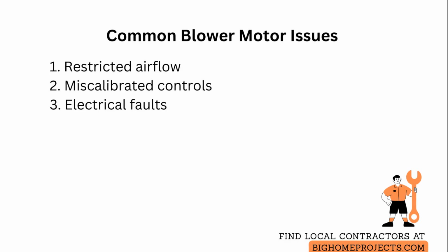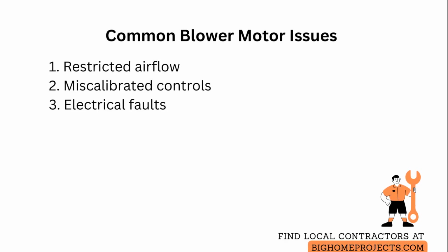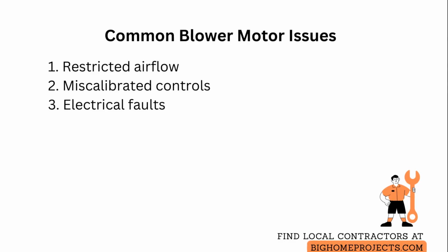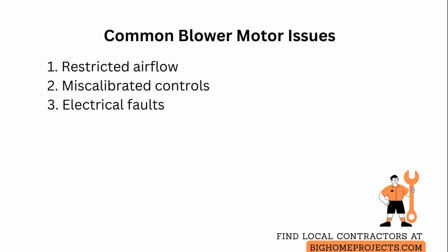For wiring shorts, bad relays, or motor start capacitor failure that keep the blower engaged, turn off power, visually inspect and tighten connectors, and if the capacitor is bulged or the relay sticks, replace the component with an exact specification match.